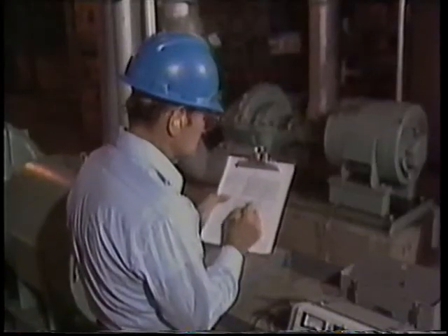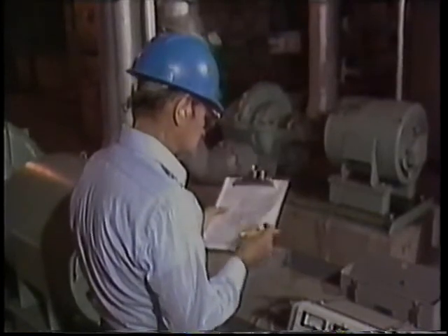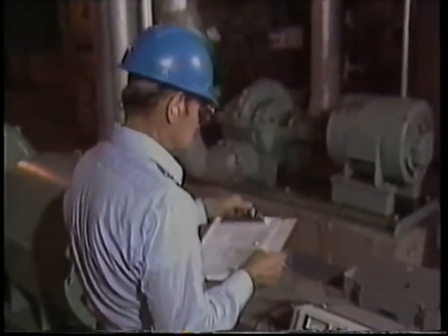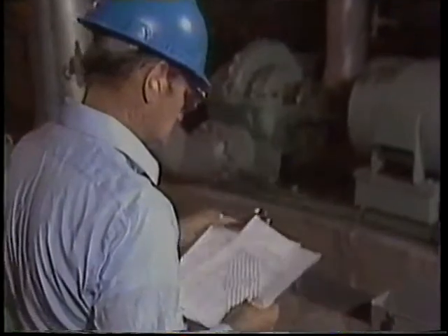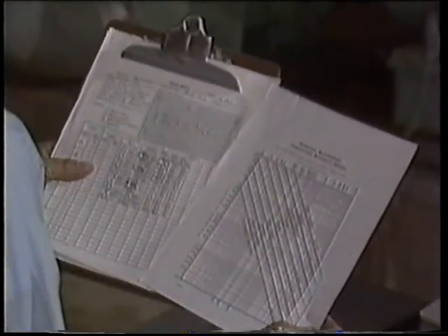So, a severity chart is a first step in evaluating the vibration readings you obtain. A severity chart can be used to determine the operating condition of equipment based on vibration readings. However, a severity chart cannot help you determine the cause of the problem. In order to determine the cause of a vibration problem, you have to analyze the vibration. In the next segment, we'll see how to use a vibration analyzer. But for now, stop and review the material you've seen here.